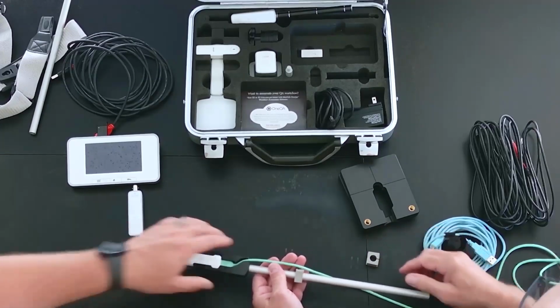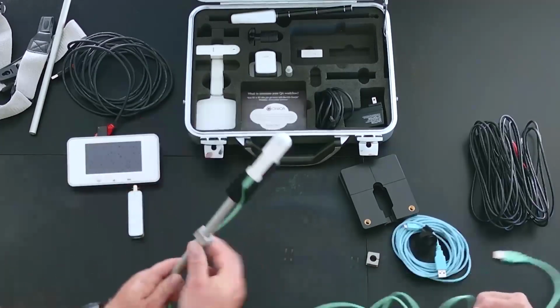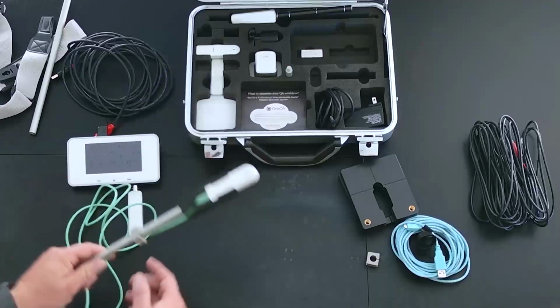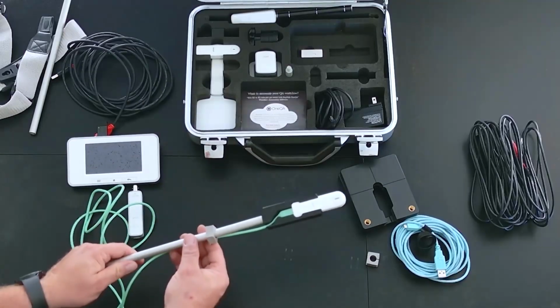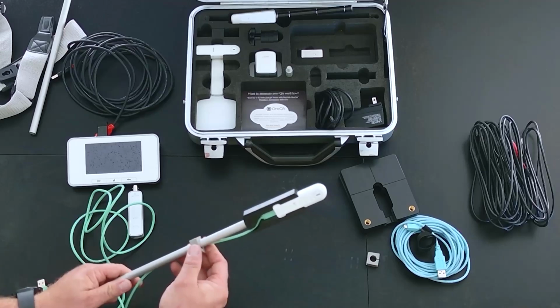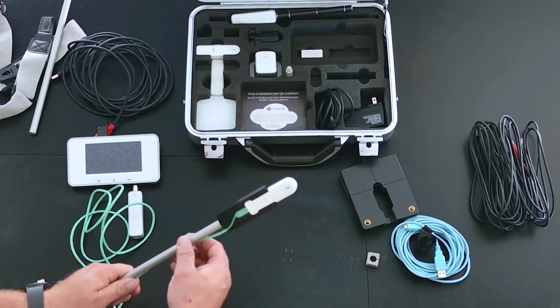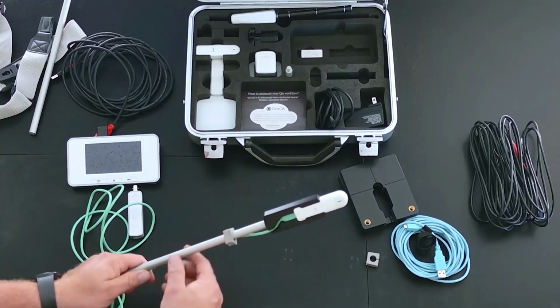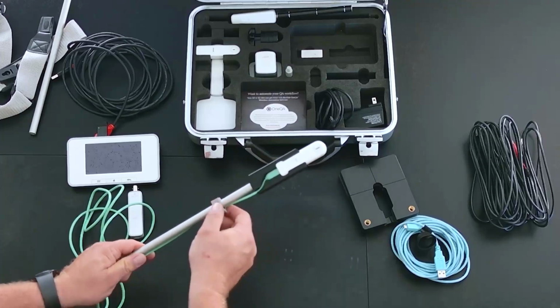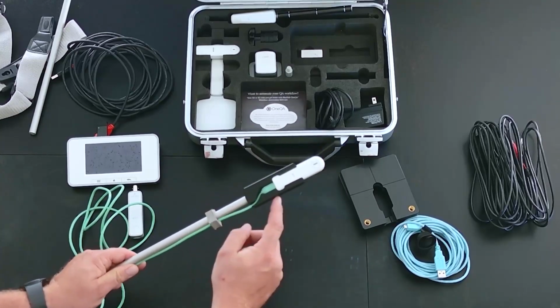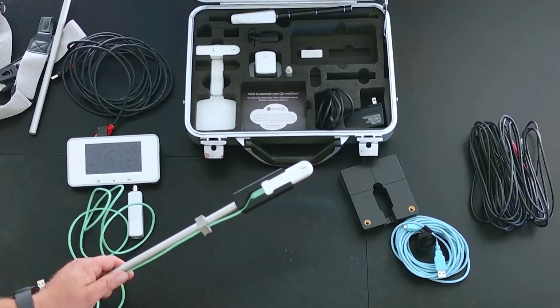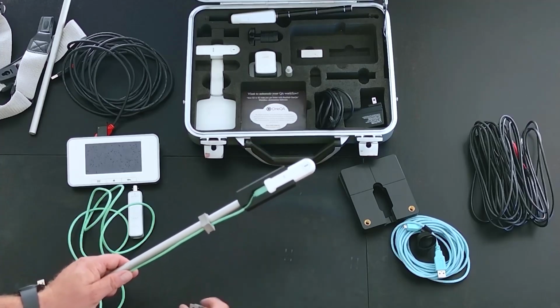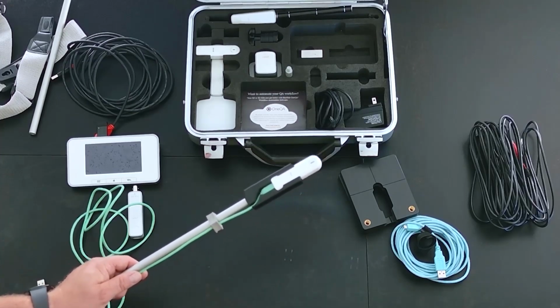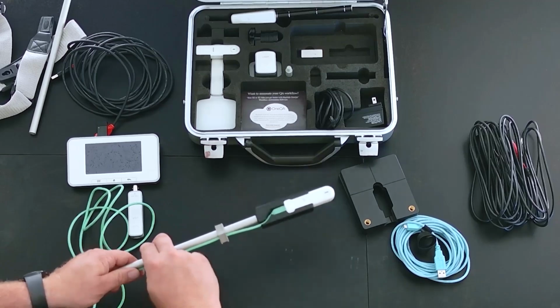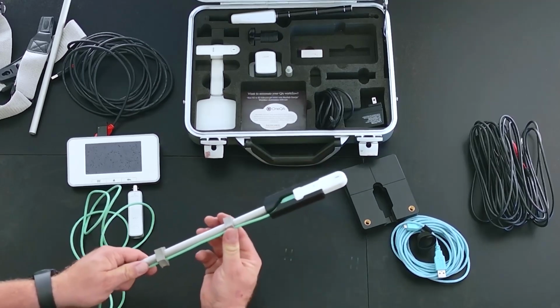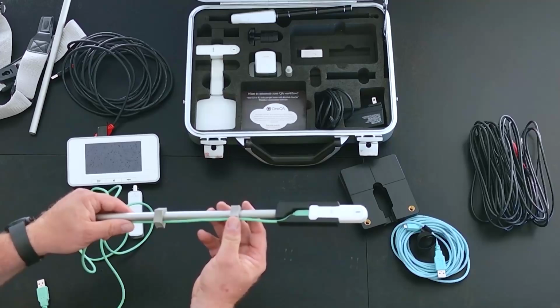Oh, what am I missing? So I was working on a cath lab with a customer, and we didn't have the right adapter. Over the cath lab, you have to put a filter over the II when you're doing the calibration, so you don't burn out the II. There is a holder built to hold your sensor there. But the problem is our rod is the wrong diameter, and we didn't have the correct holder. So instead of going home, we figured out that if we put these two little rubber blocks on here, because they squish and compress, I was able to click this into place on that II filter.